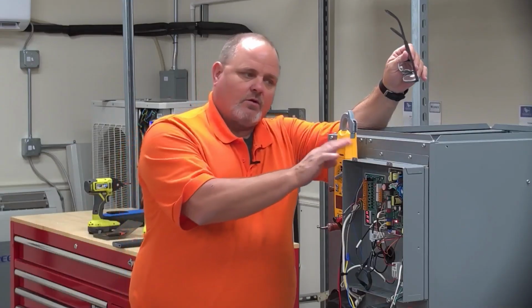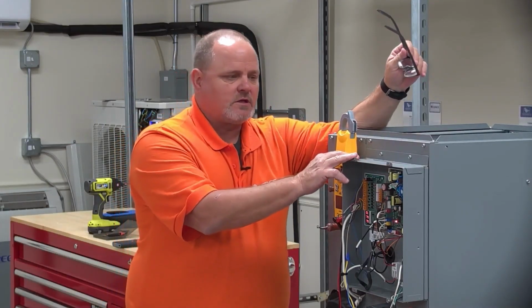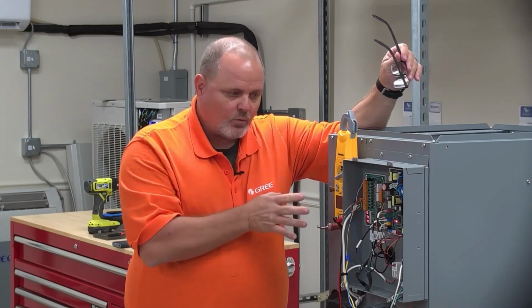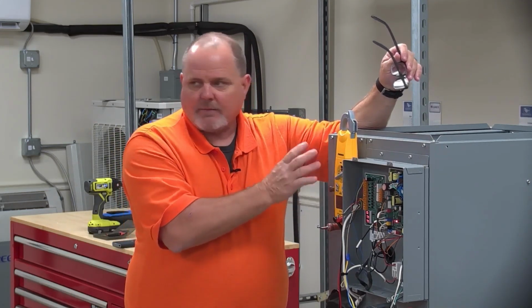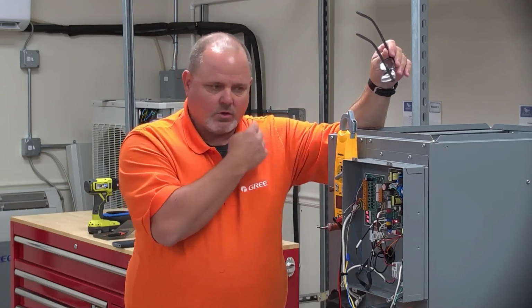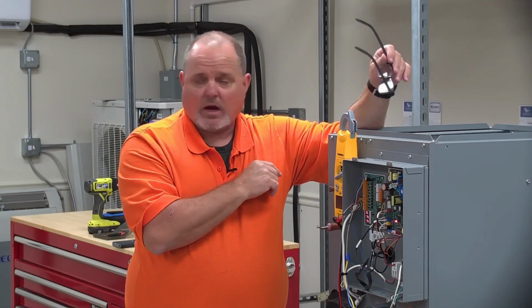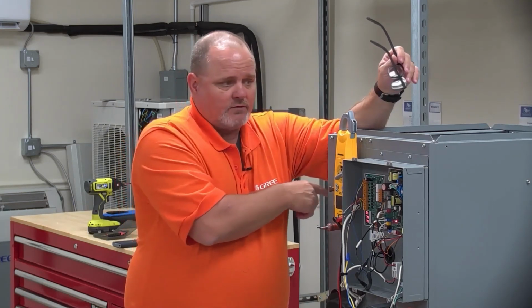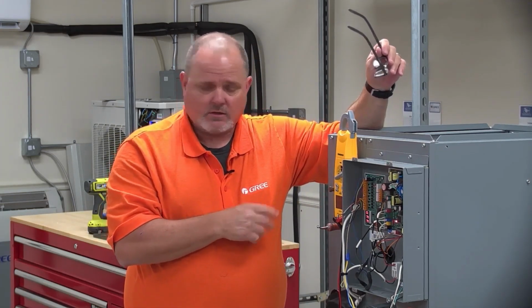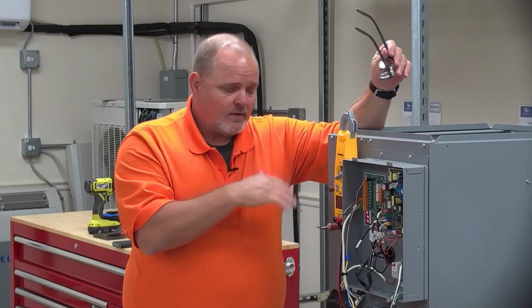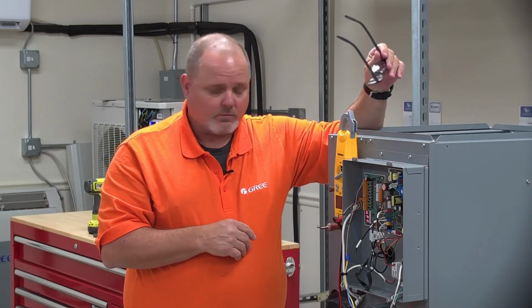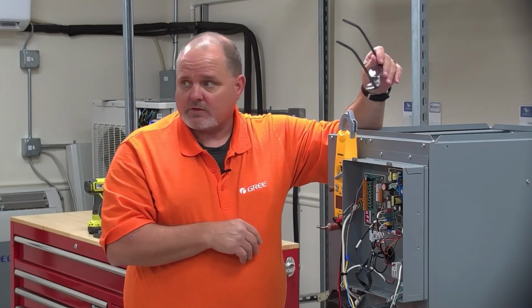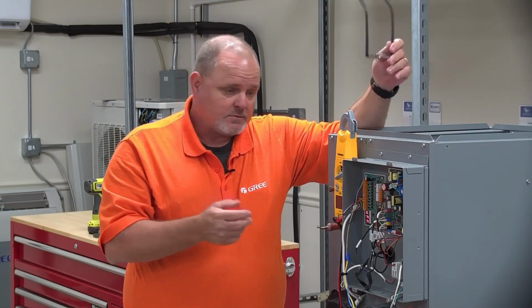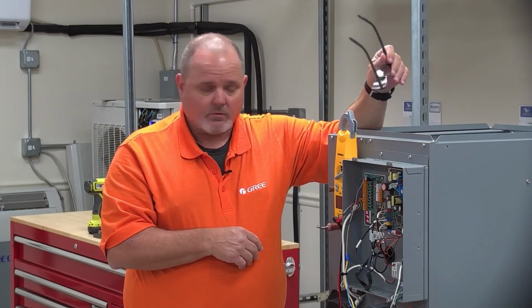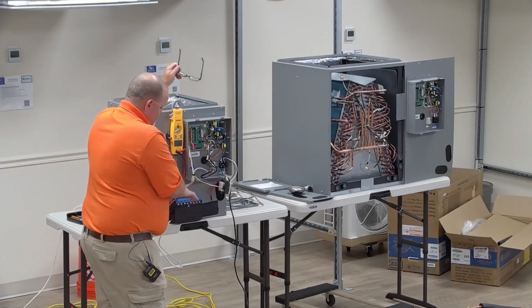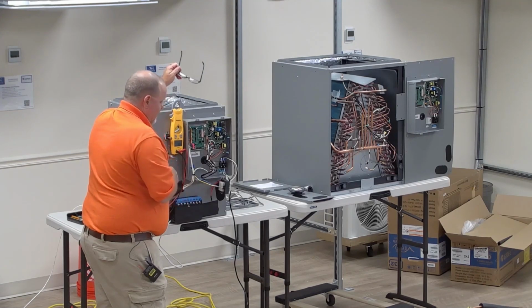Yep. And again, the only thing that Daniel and I, when we first looked at these, we didn't like the idea that the only option was the control panel on the front. So they had to make those wires a little longer for us, and then give us pre-punched holes on the sides so that the box can be moved to the left or the right. That way it can't interfere with your flue piping, which, especially if you've got a condensing furnace, could really be an issue. Or even an 80% furnace, depending on what kind of clearance you've got.